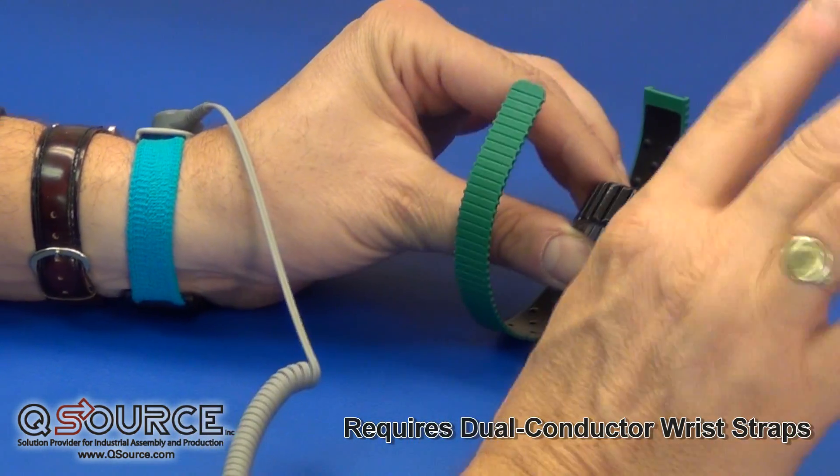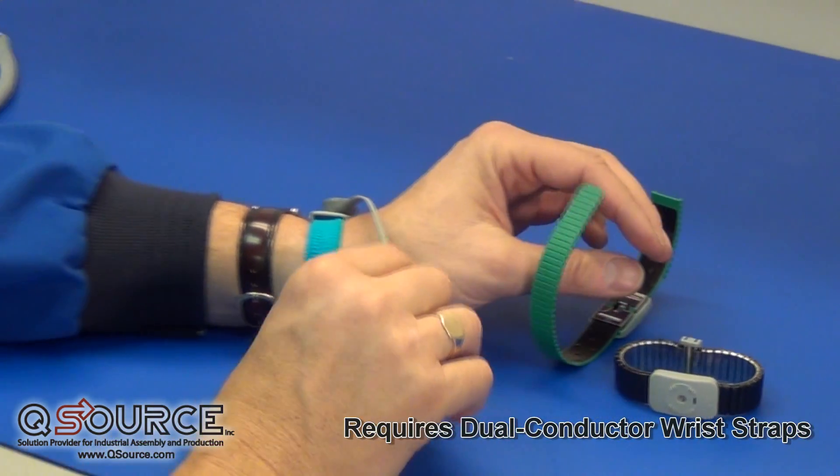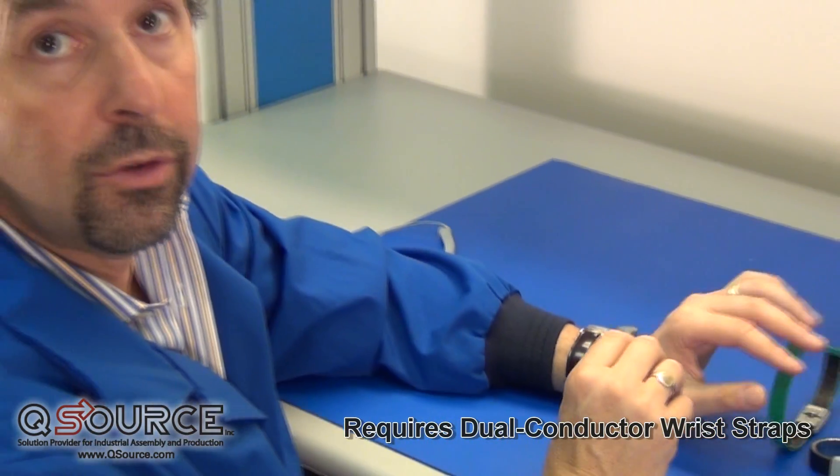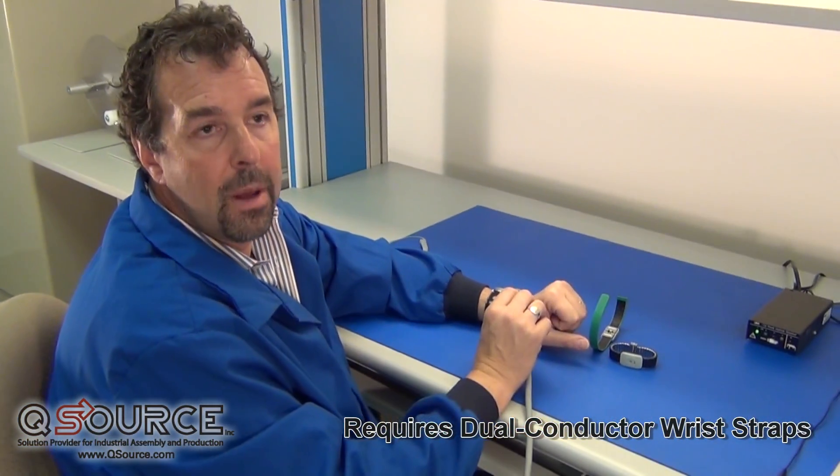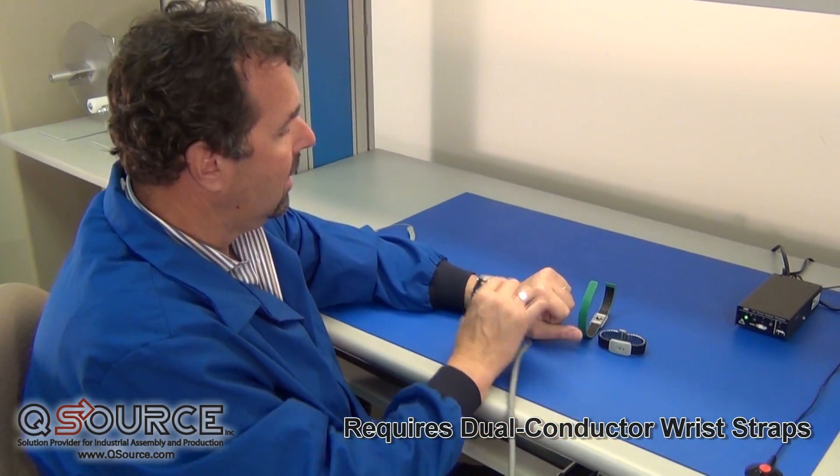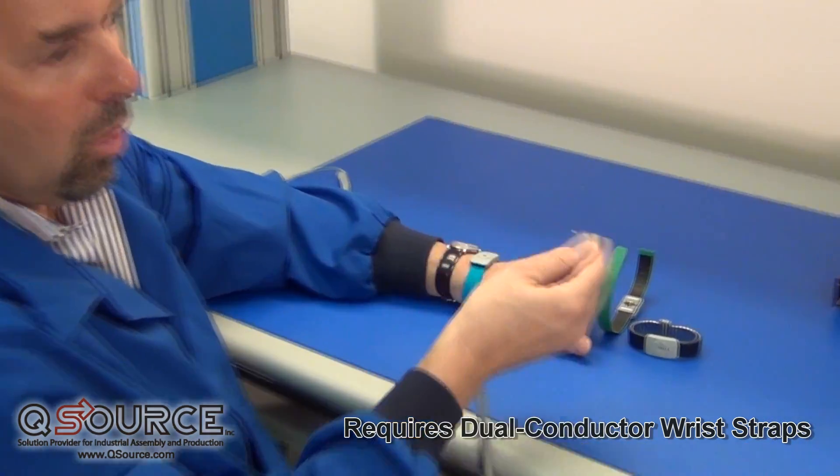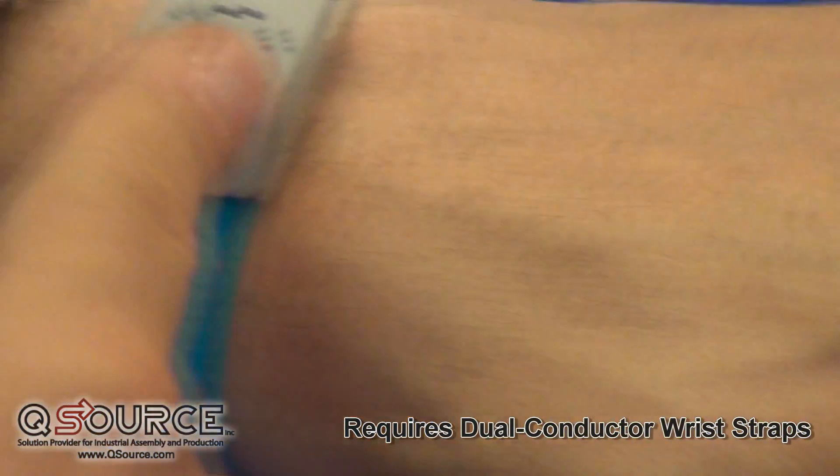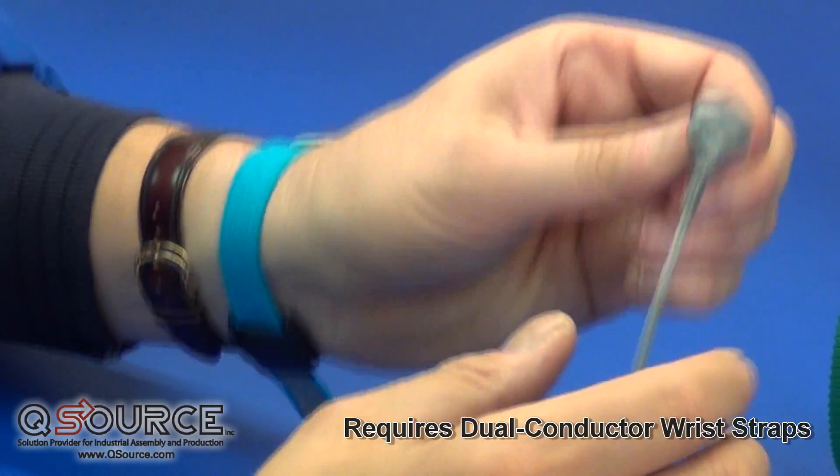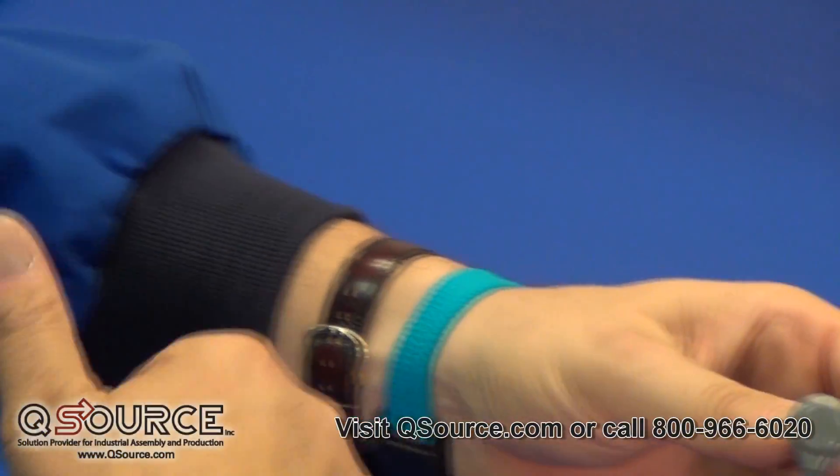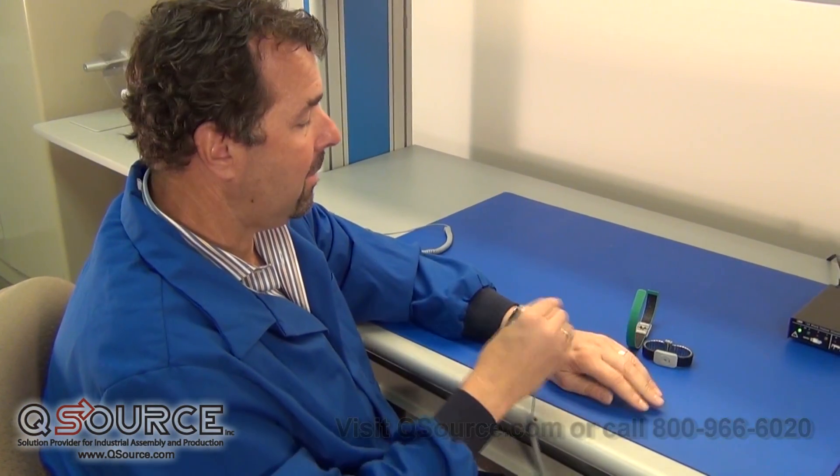All of the wrist straps with these constant monitors are dual conductor wrist straps. They will not accept the standard banana plug jack. They require special cords and matching wrist straps, which are two-wire. They look the same to an operator. However, they are two-wire because they complete a loop where we're testing the operator at all times.